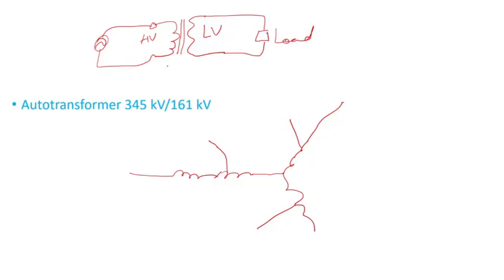In a pure two-winding transformer, the two windings are not connected electrically — they are only magnetically coupled. When you apply voltage, flux flows through the core and induces voltage in the low voltage winding. In an auto transformer, however, there is a series winding that is electrically connected to a common winding. The H1 terminal includes the series plus common winding, while the X1 terminal has only the common winding, but they are electrically connected.